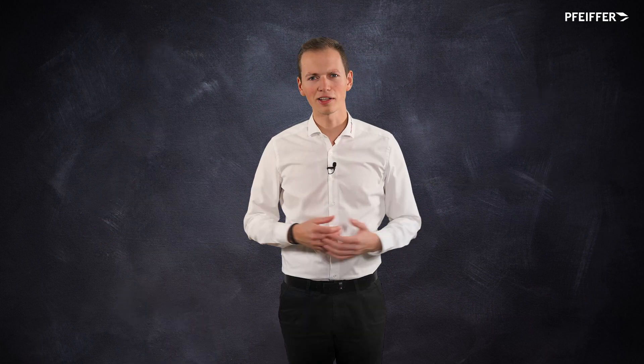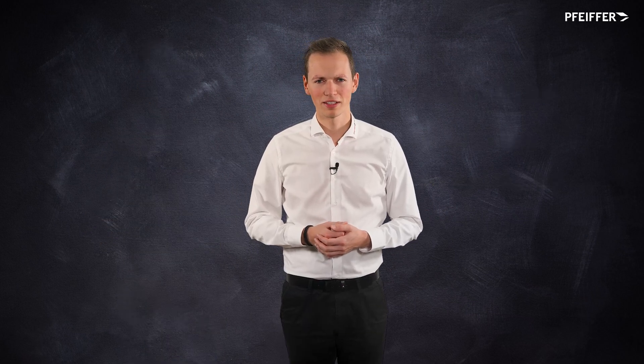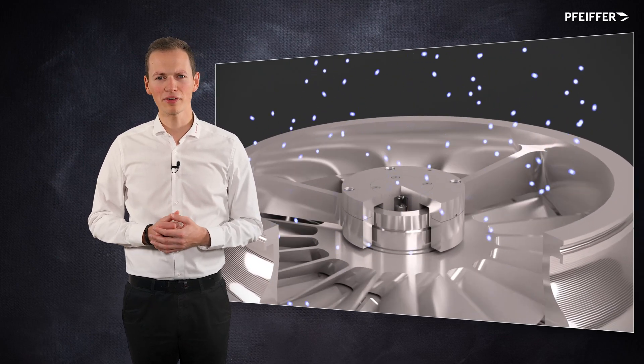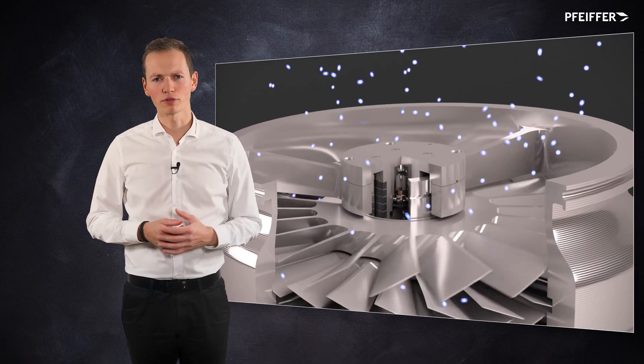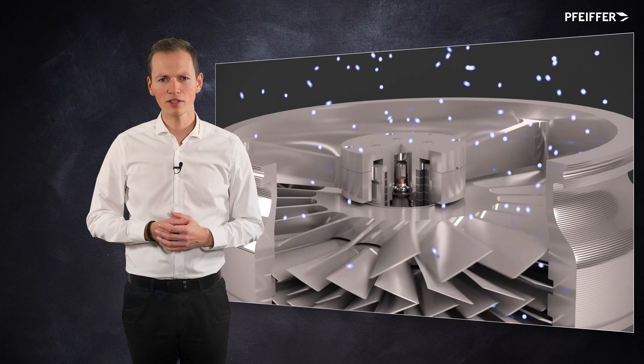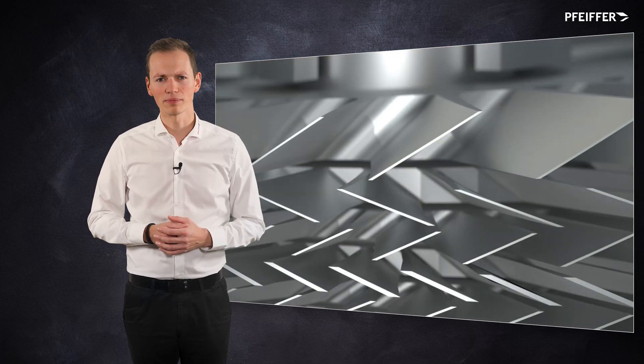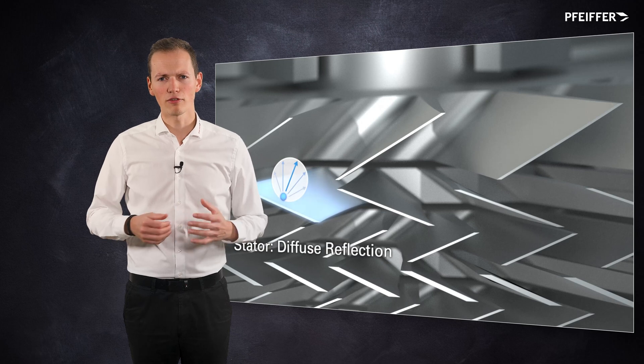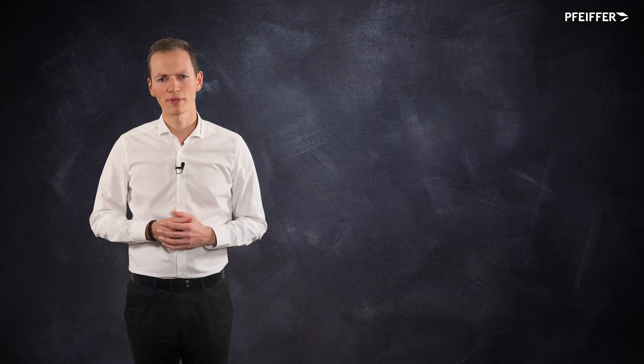Let's take a closer look at the compression ratio for turbo pumps. The pumping action of a turbo pump is based on the fact that more gas particles flow from the high vacuum side to the fore vacuum side than the opposite way around. This is achieved by the acceleration of particles by the fast rotating rotor blades.